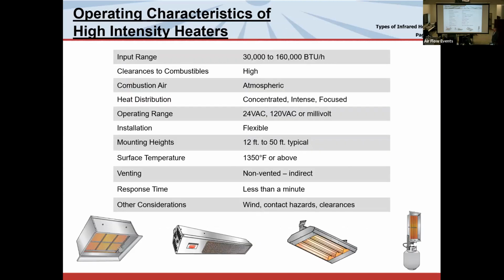I'm not going to go through this in great detail, but the BTU range is shared. Controls are optional. Probably what I want to point out is mounting heights, 50 feet all day long. We do it all the time. Airplane hangars. As a matter of fact, I was at a facility in Russia and we were putting heaters 120 foot off the floor. They had a mezzanine level in the middle and we did a second row.